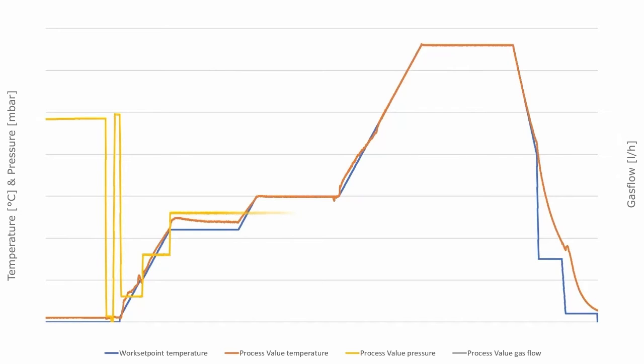It is important that the furnace performs a pre-program, represented by the yellow line. First, the furnace is evacuated down to 20 millibars to perform a leakage rate measurement. Once successful, the furnace is evacuated for a defined time to reduce the remaining oxygen level as much as possible.